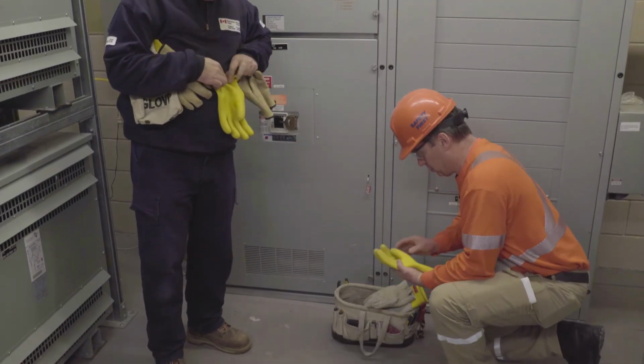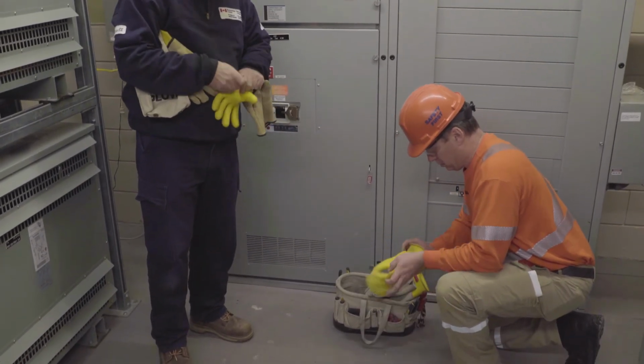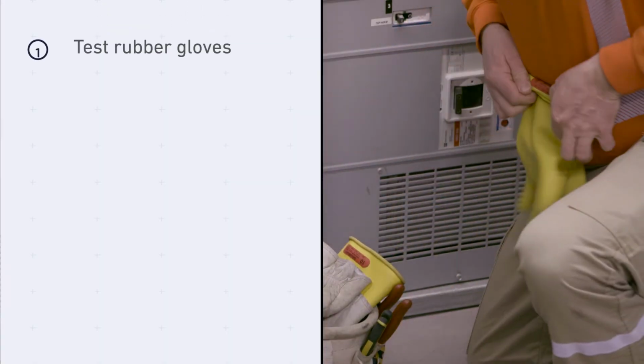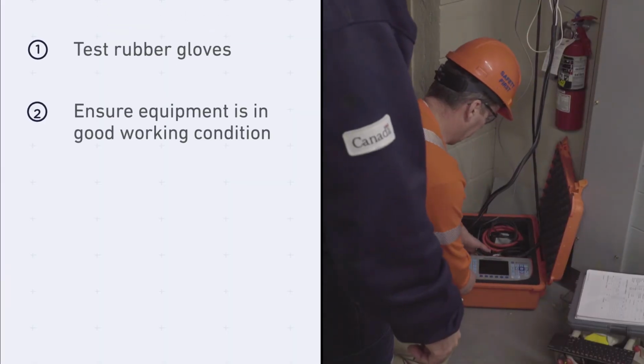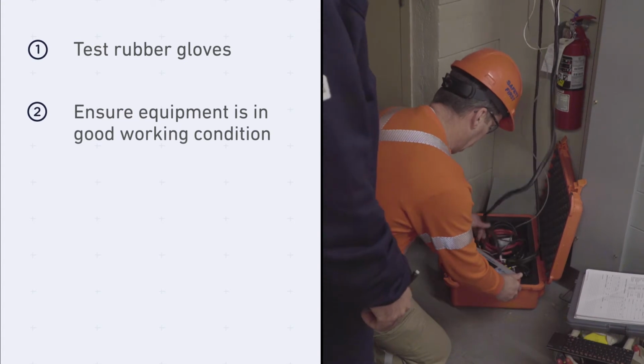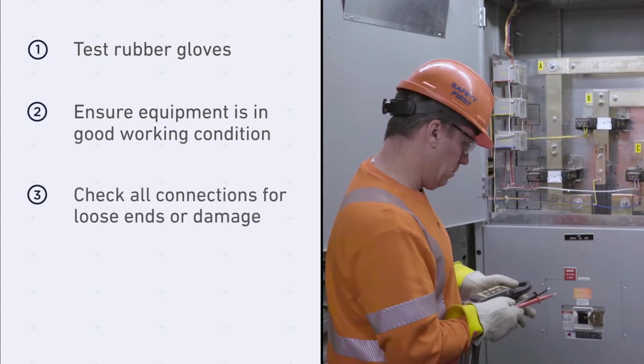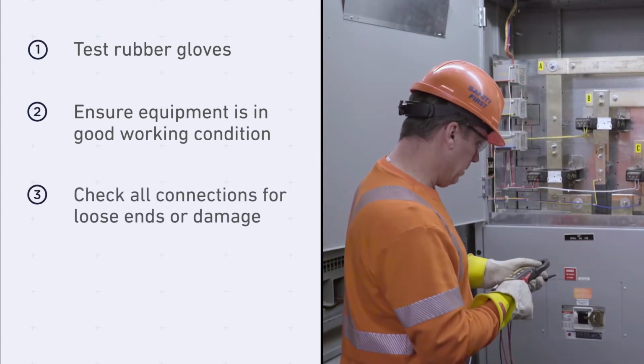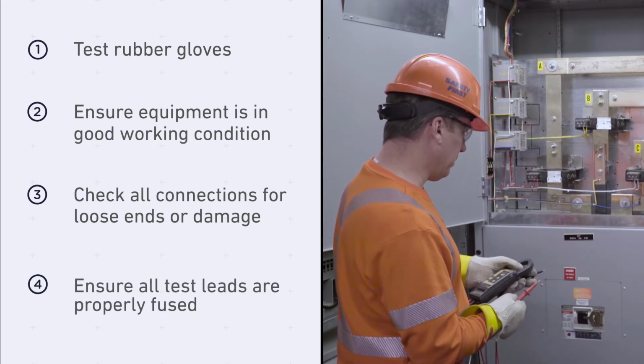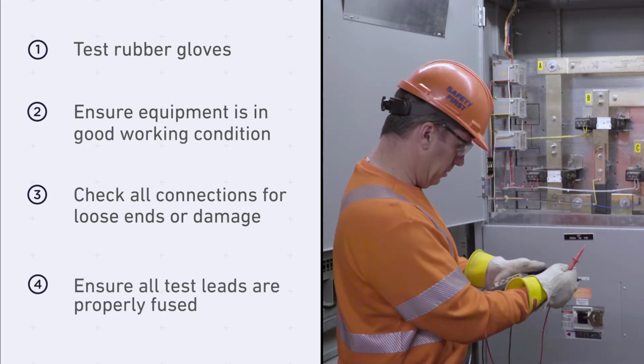Prior to performing any dynamic tests or voltage measurements, always: 1. Test your rubber gloves. 2. Ensure all of your equipment is in good working condition. 3. Check all connections for loose ends or damage. 4. Ensure all test leads are properly fused.